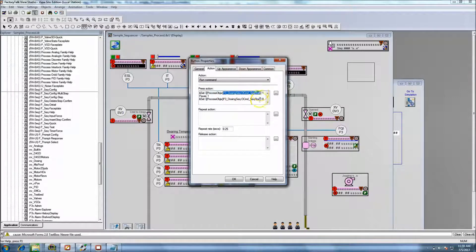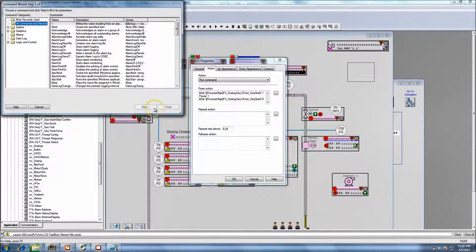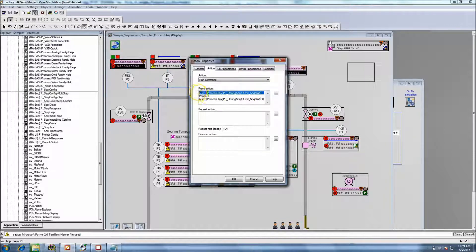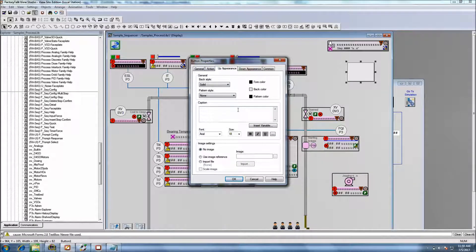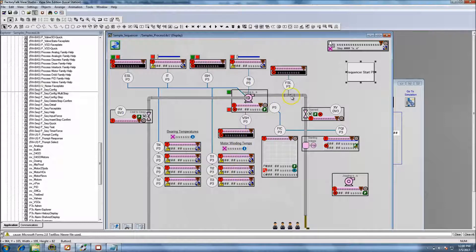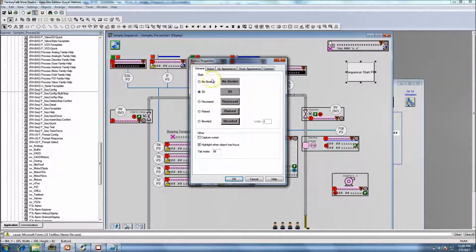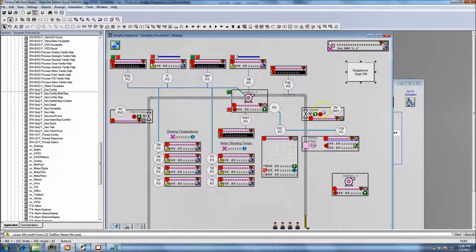What that does is: as soon as you press it, it sets a one to this bit via the run command, then it pauses for one second, then it sets a zero to that bit. So no matter if you have a control lag or a communications lag, this is the best route to go about it. Let's put some text on this button and call it 'sequence start push button' so you can easily see it.